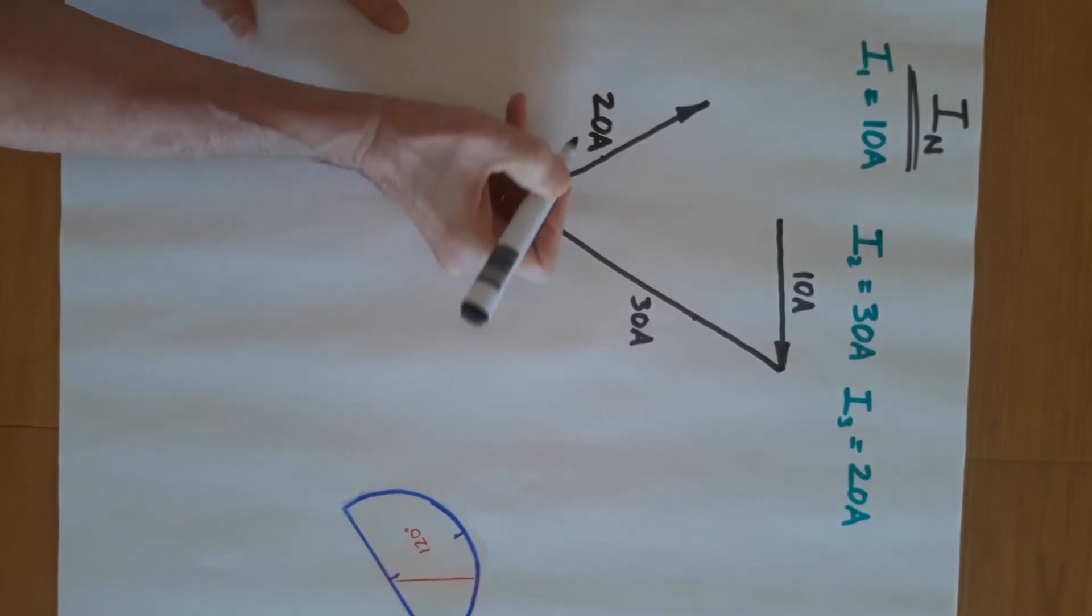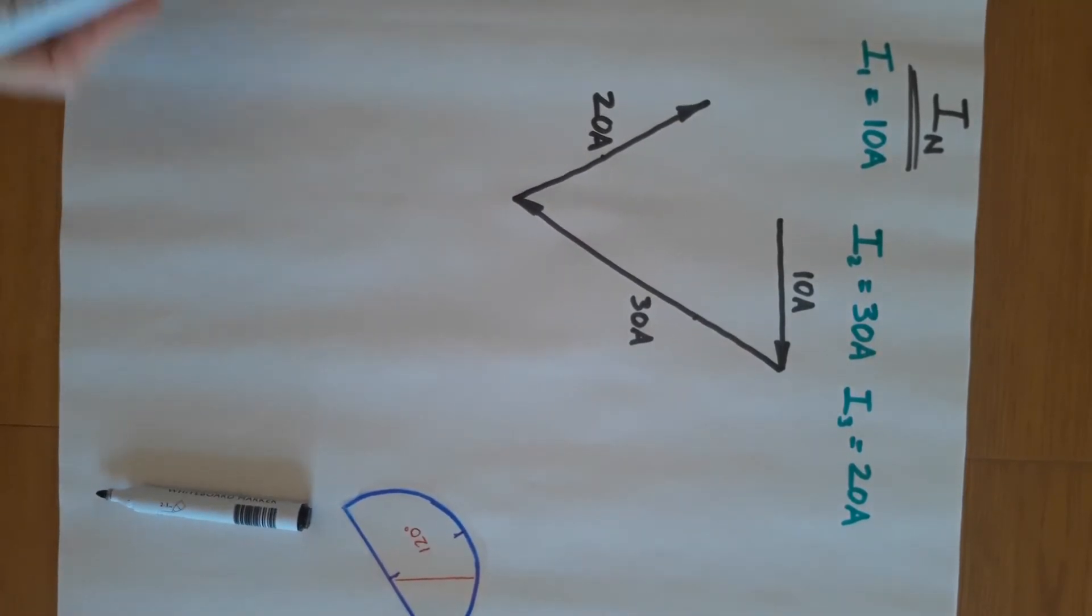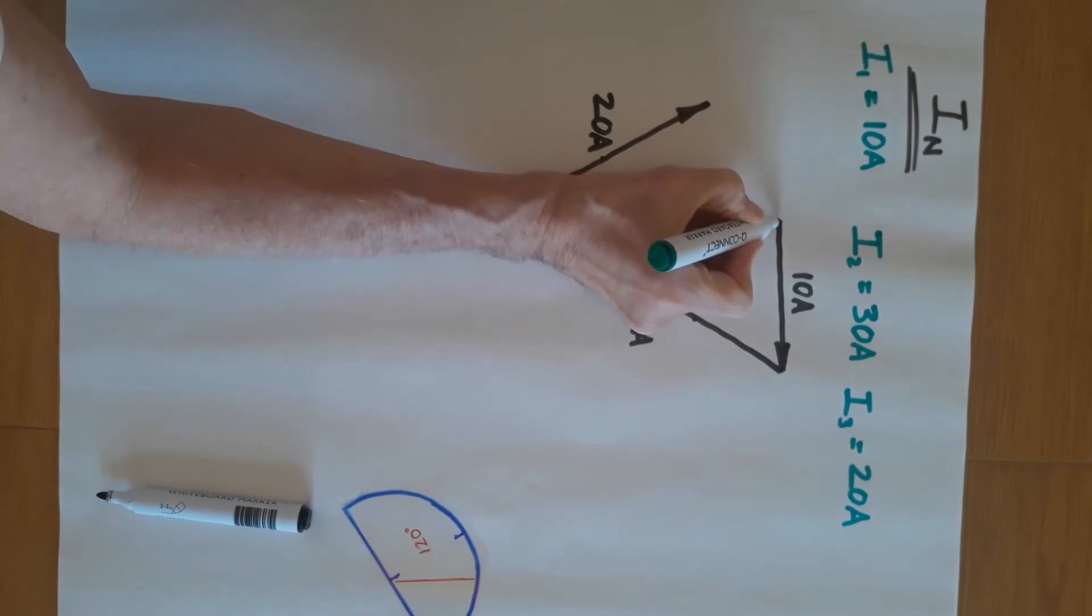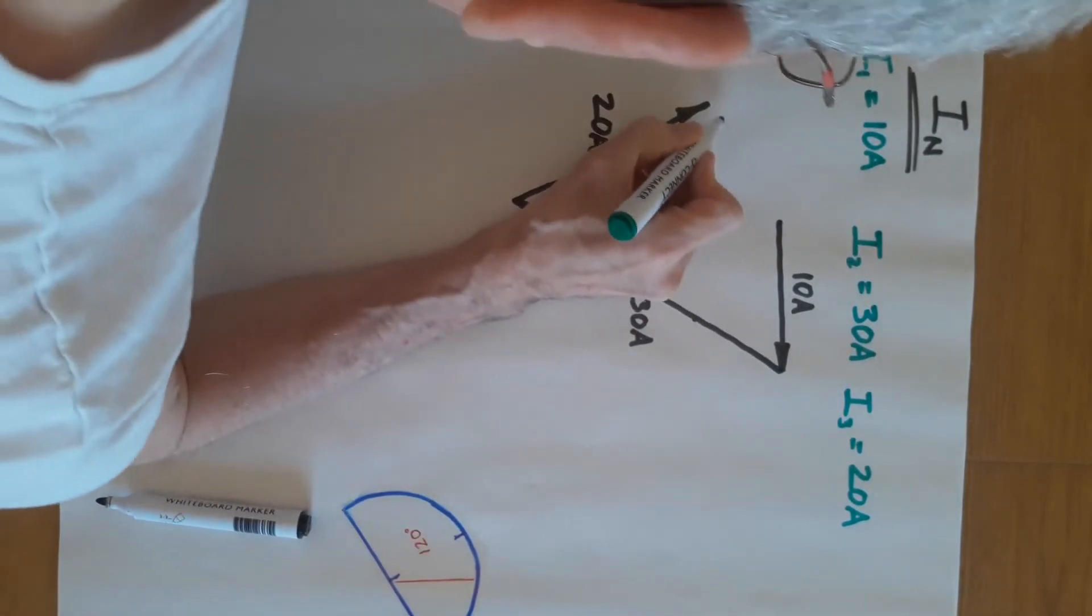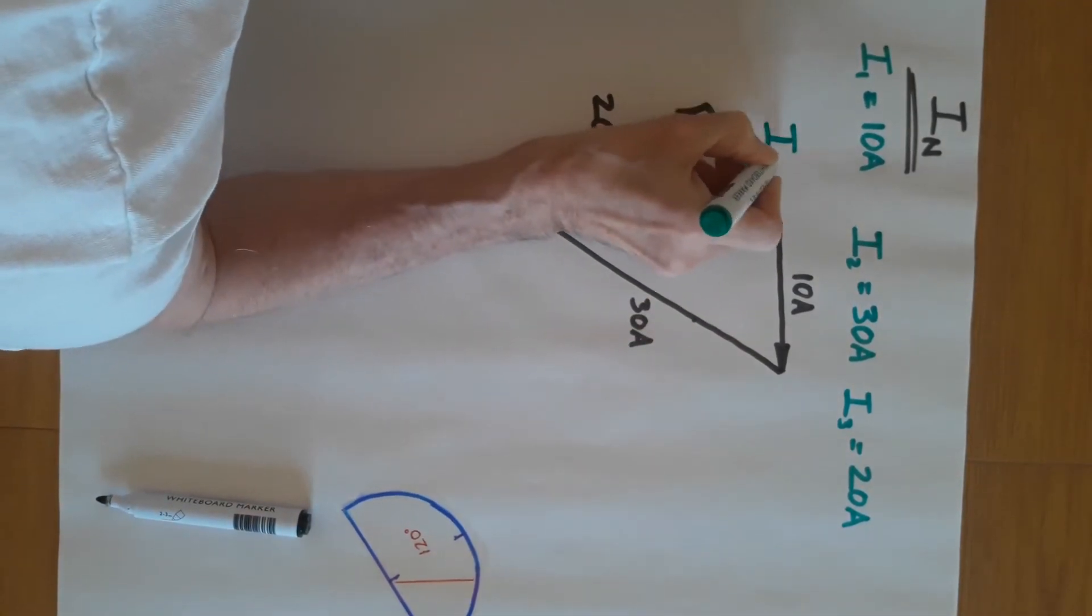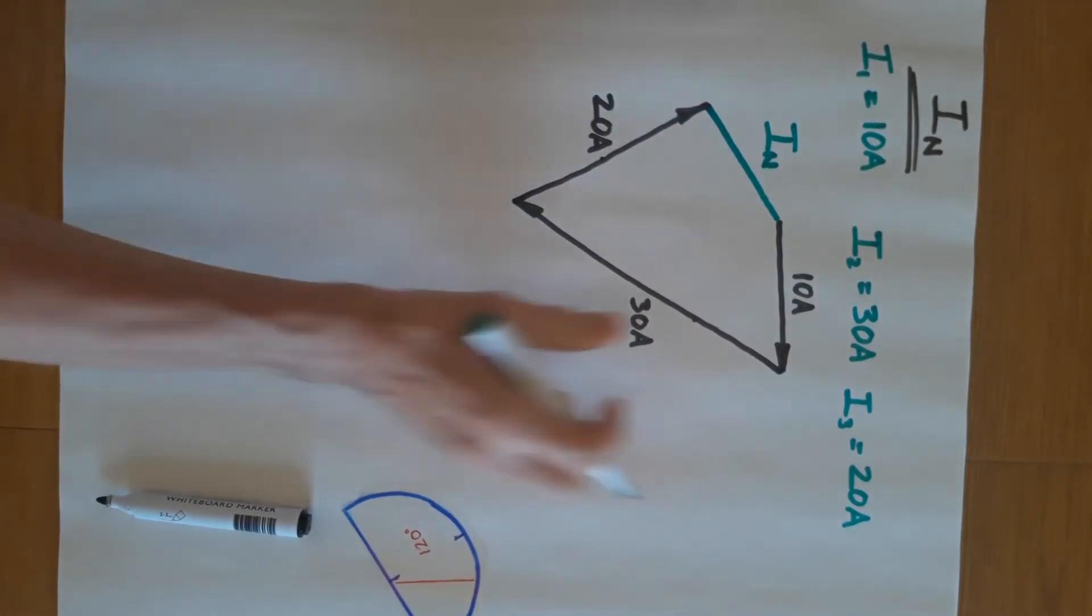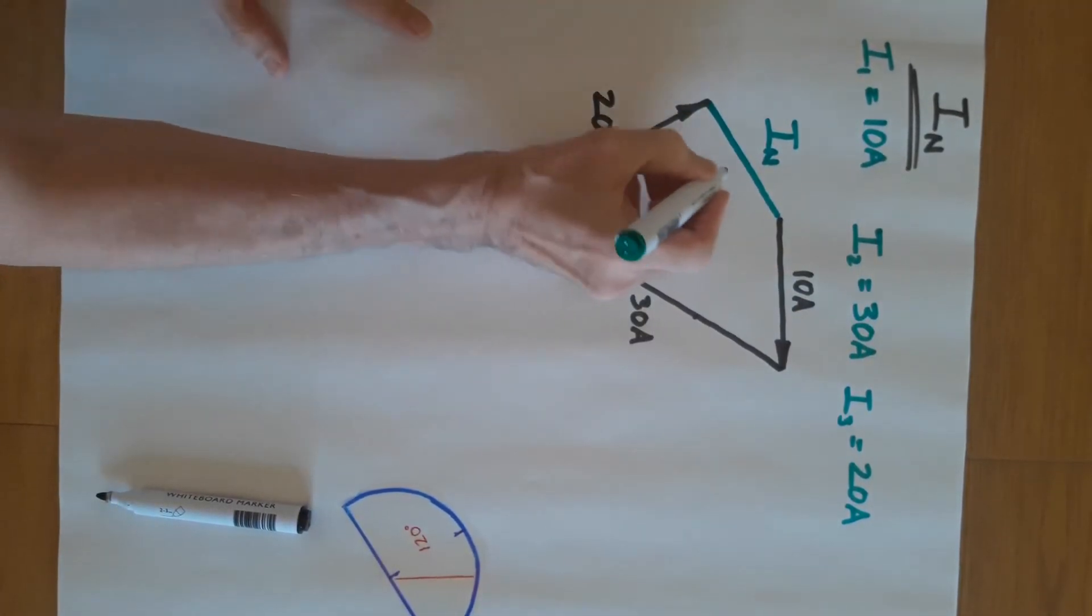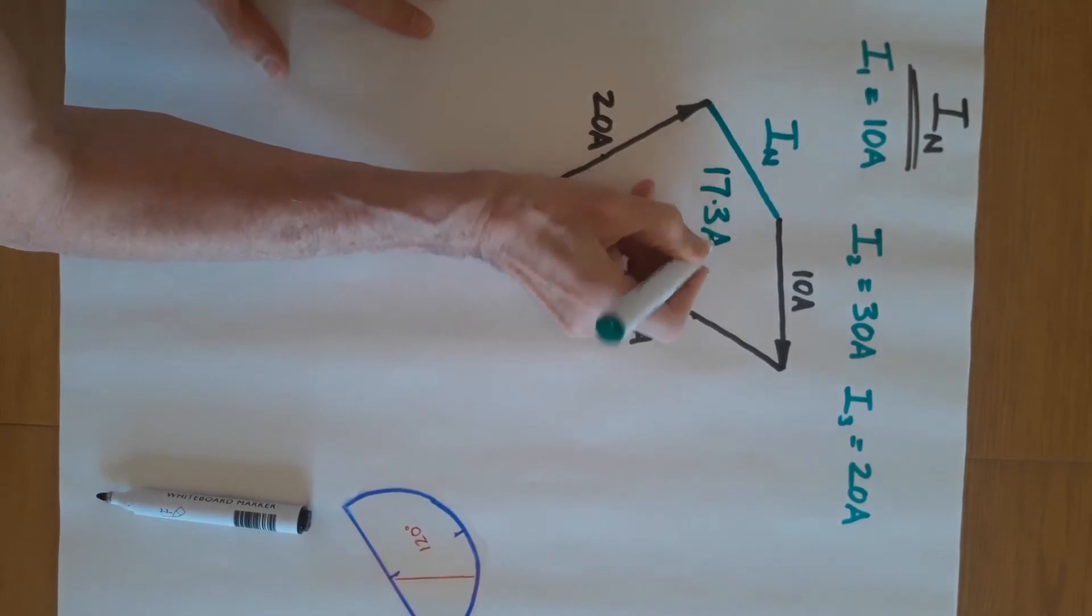And the whole purpose of this diagram is the difference from where you started to where you finished is your neutral current. So this is I_n, the neutral current. And you measure it, and if you've done this accurately, you should come up with 17.3 amps.